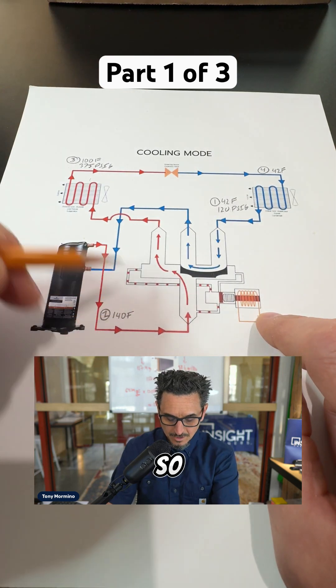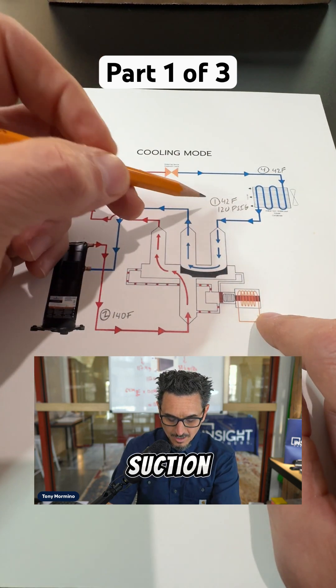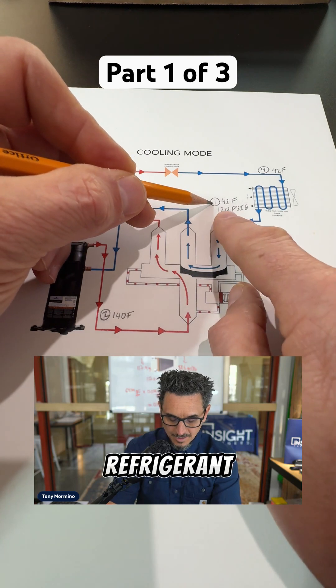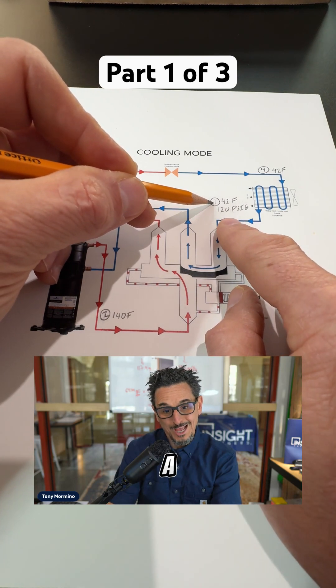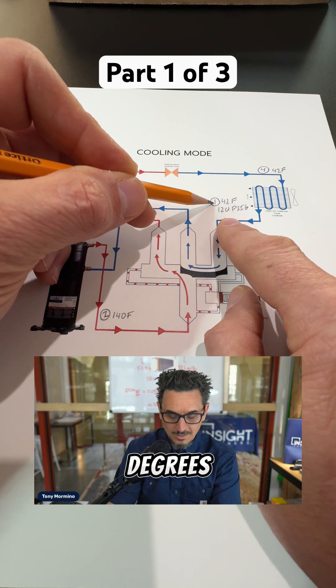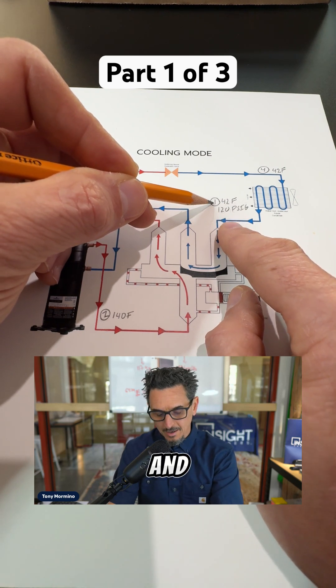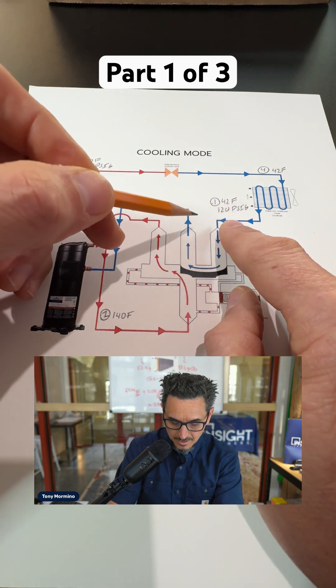Let's walk through the function of each of these. I like to start with the suction line, which is the refrigerant leaving the evaporator. In this case, we're going to look at 410A, which is about 42 degrees leaving and approximately 120 PSI.